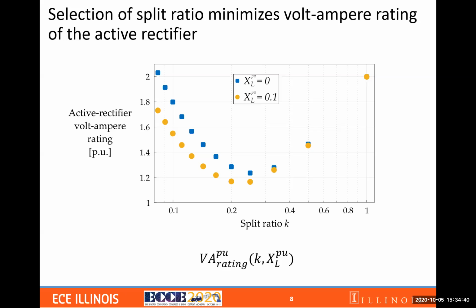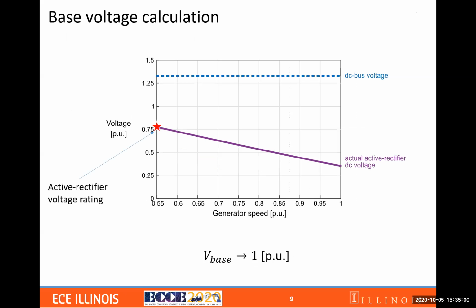For our work, we decided to go the second route because at high power level, the options for the switch voltage are very limited. So we want the power electronics to decide the voltage level such that we best utilize the power electronic switch. And if we take that route, the voltage level could be decided by looking at the active rectifier voltage rating. According to the work so far, at the minimum generator speed, the active rectifier has the highest voltage rating in per unit. For example, in the system here, at the minimum speed of 55% of the rated value, the per unit voltage of the active rectifier is going to be 0.75.